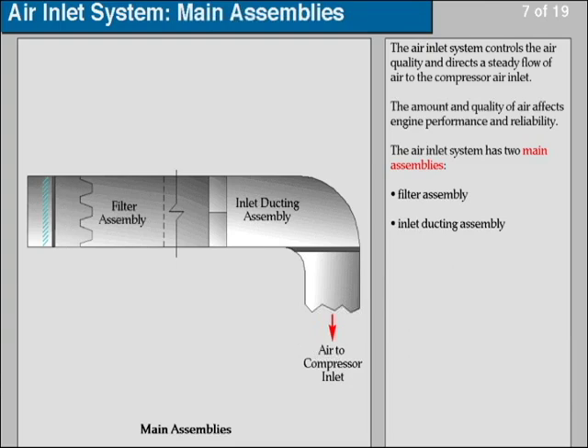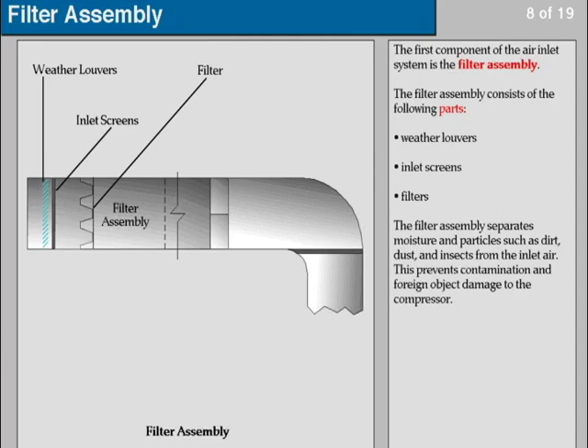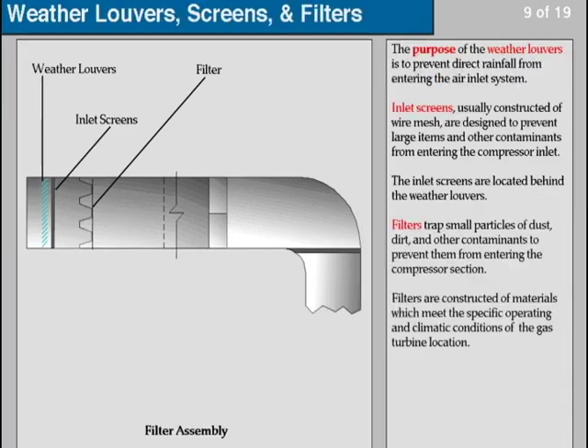The air inlet system has two main assemblies: the filter assembly and the inlet ducting assembly. The first component of the air inlet system is the filter assembly, which consists of the following parts: inlet screens, weather louvers, and filters. The filter assembly separates moisture and particles such as dirt, dust, and insects from the inlet air, preventing contamination and foreign object damage to the compressor. The purpose of the weather louvers is to prevent direct rainfall from entering the air inlet system.